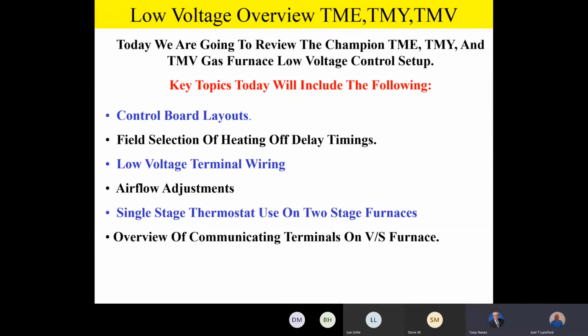We're going to talk about the low voltage terminal wiring. This is very, very important. I believe if a technician can get his head wrapped around how to wire the thing, low voltage, especially the control voltage, he'll be a much better technician. And if he does have issues, he'll be able to identify those problems much quicker if he understands the low voltage wiring. We're going to talk about airflow adjustments and how to set the furnaces up for different airflow scenarios.